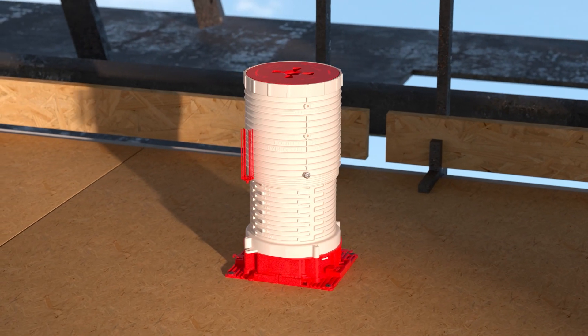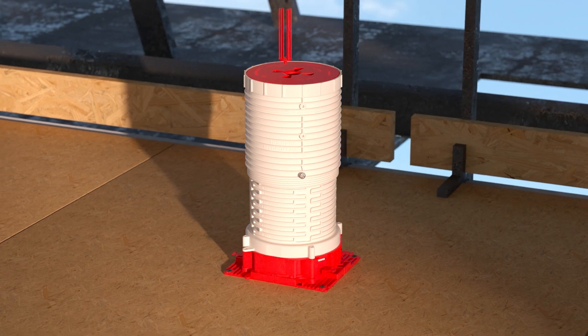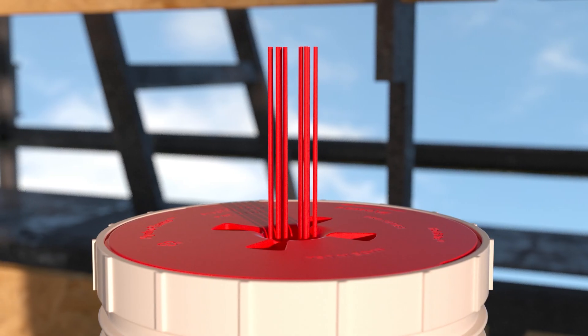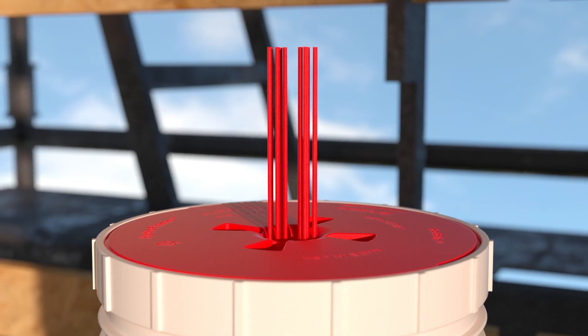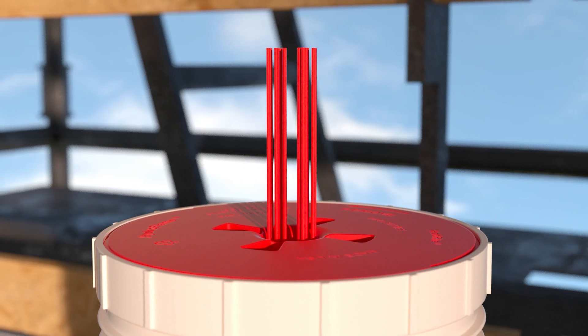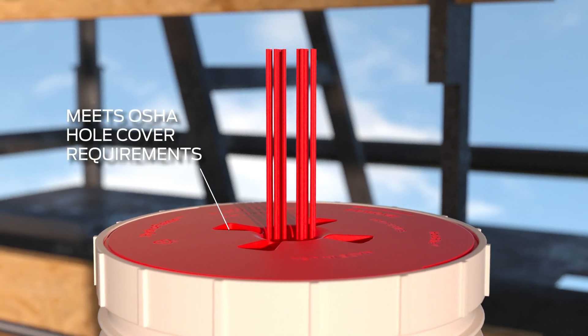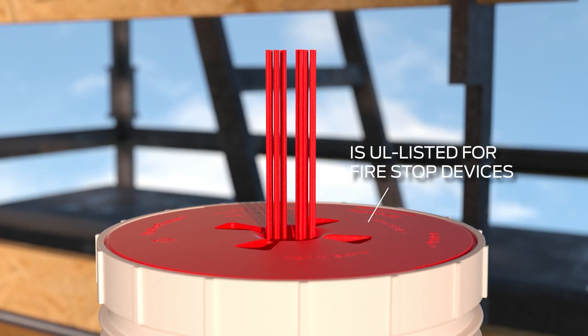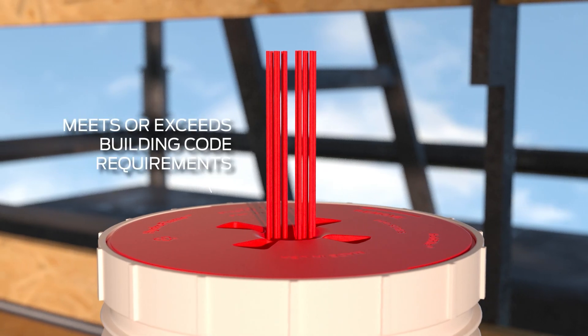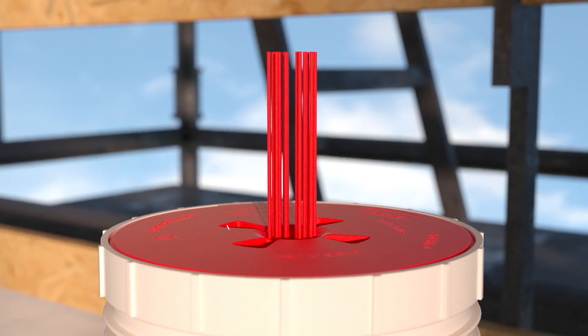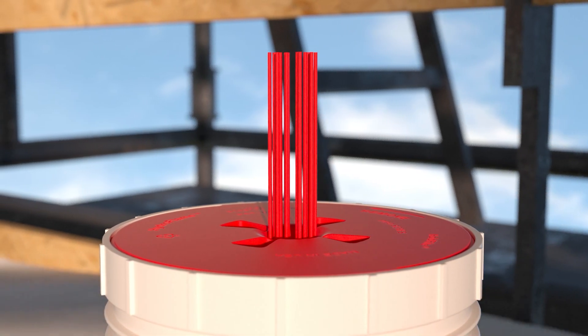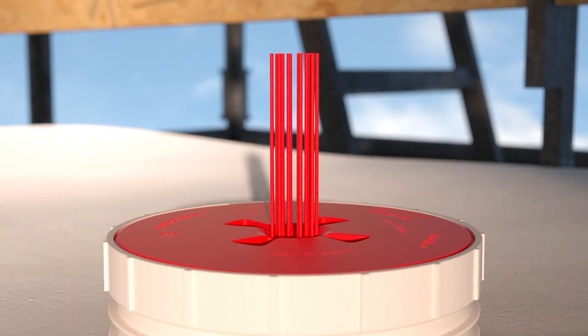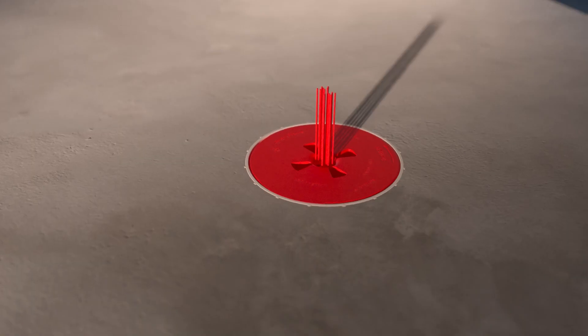Next, remove the locator whiskers from the base and press them firmly onto the center of the safety cap. The Hydro Flame Pro safety cap from HoldRight meets OSHA hole cover requirements, is UL-listed for firestop devices, and meets or exceeds building code requirements. The whiskers allow you to easily locate penetrations after the slab has been poured.